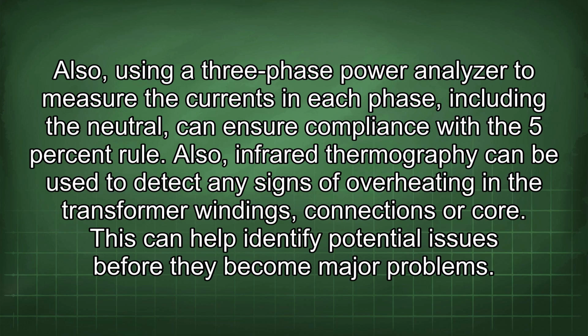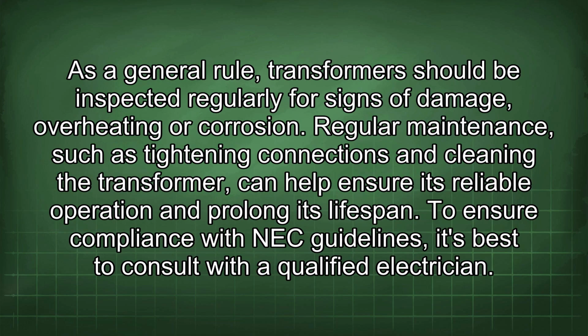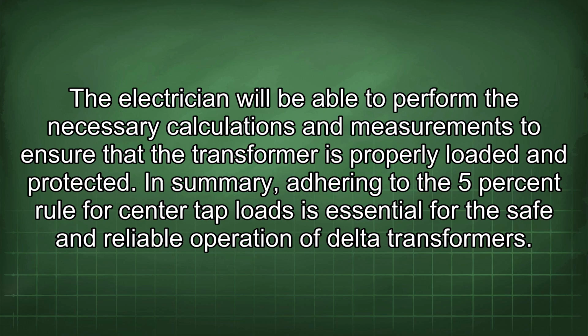with the 5% rule. Also, infrared thermography can be used to detect any signs of overheating in the transformer windings, connections, or core. This can help identify potential issues before they become major problems. As a general rule, transformers should be inspected regularly for signs of damage, overheating, or corrosion. Regular maintenance, such as tightening connections and cleaning the transformer, can help ensure its reliable operation and prolong its lifespan. To ensure compliance with NEC guidelines, it's best to consult with a qualified electrician.